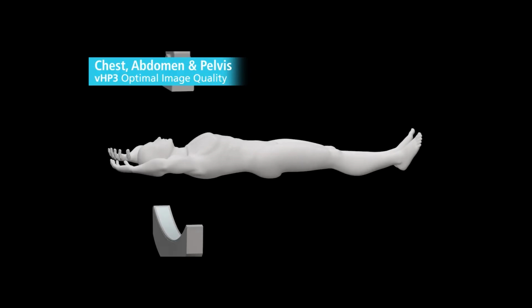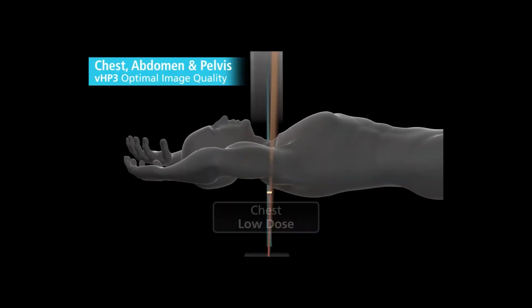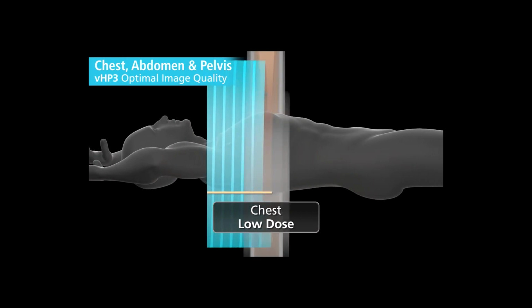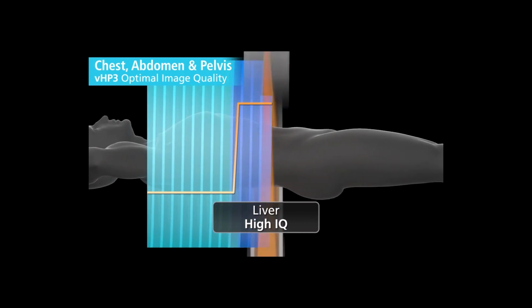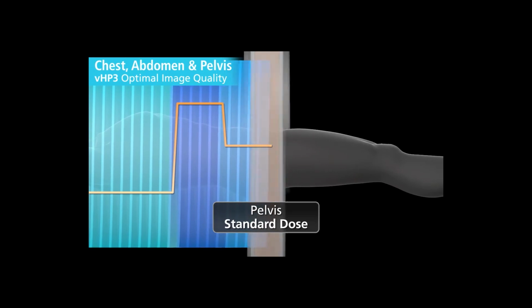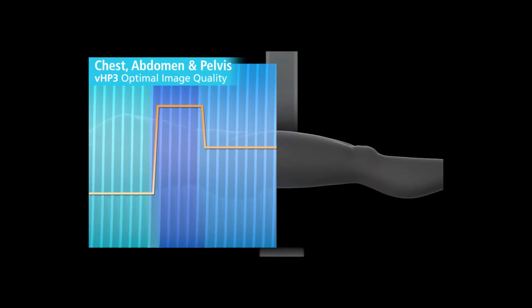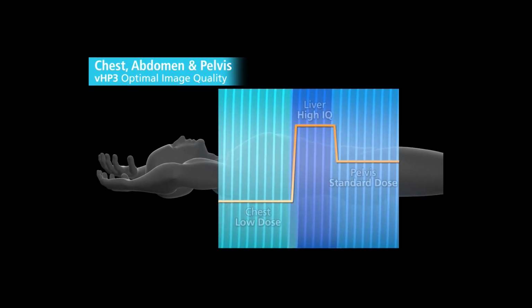The Aquilion Prime SP features our unique variable helical parameters technology. During a normal helical scan, typically scan parameters are fixed. What we're able to do is change these settings within a single helical scan. Pure Vision Optics delivers significant reduction in image noise, which enables dose reduction of around 30%. It also delivers improvements in low contrast resolution of up to 22%.